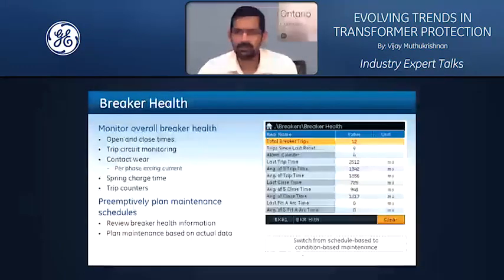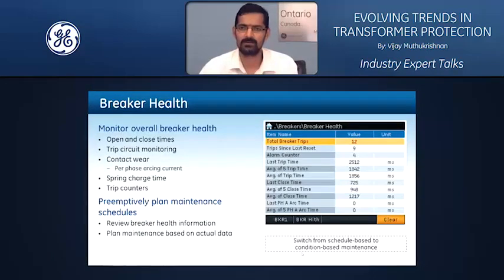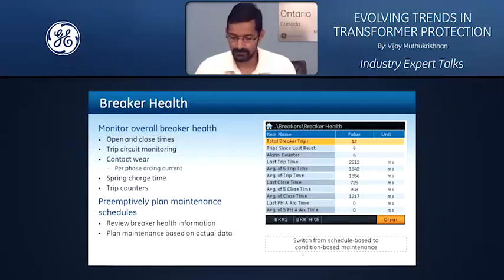The next area to look at in a transformer protection relay is what functionalities the relay can offer to monitor the health of your breaker too. It's not just the transformer that your relay is interacting with; the relay is also closing and tripping the breaker. So can the relay provide a good amount of analytics around a breaker? In the case of an 845, it can track open and close times. It provides trip circuit monitoring. It can also give you contact wear through per phase arcing current, spring charging time, and trip counters.